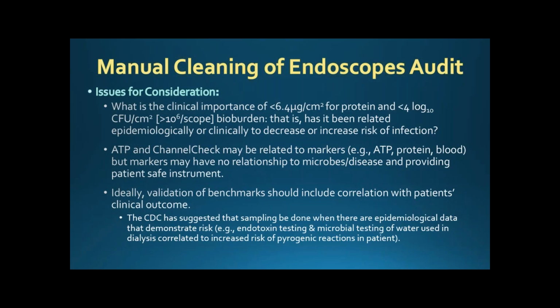Always just issues for consideration. ATP, so some people also use ATP to check to make sure, but again, ATP and channel check, those two don't tell you if there's microorganisms in there, just potentially other markers that would indicate that there was some type of a cell or a microbe present. So essentially it tells you it's not clean, but it doesn't really tell you why it's not clean.